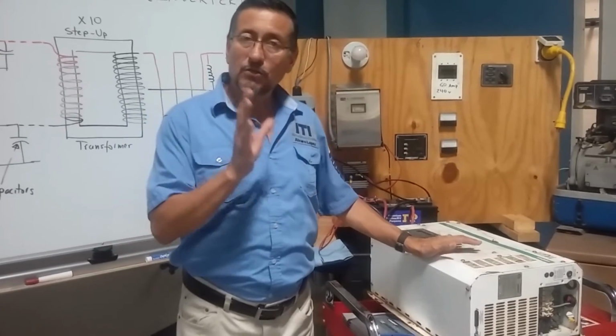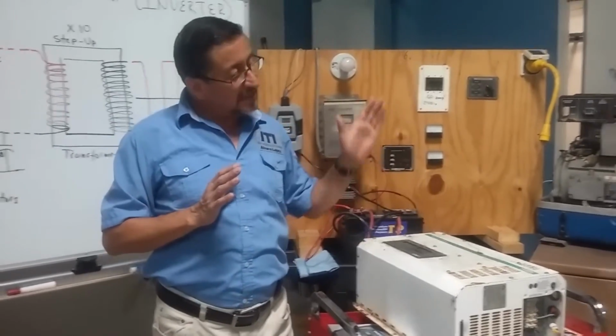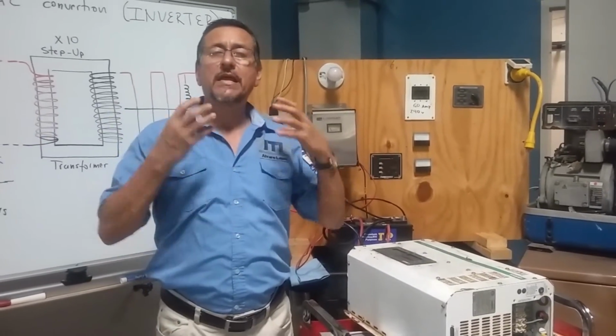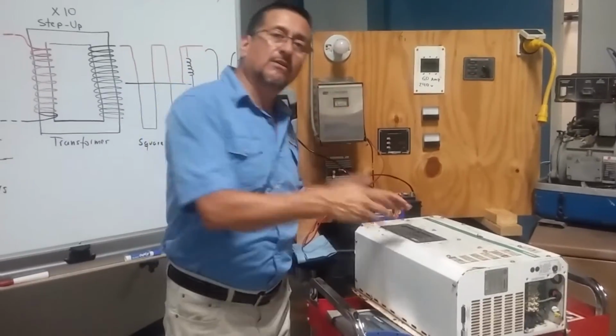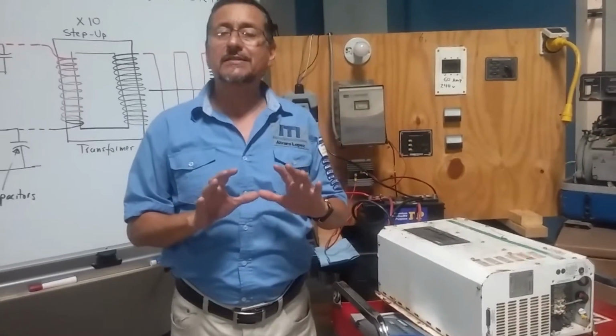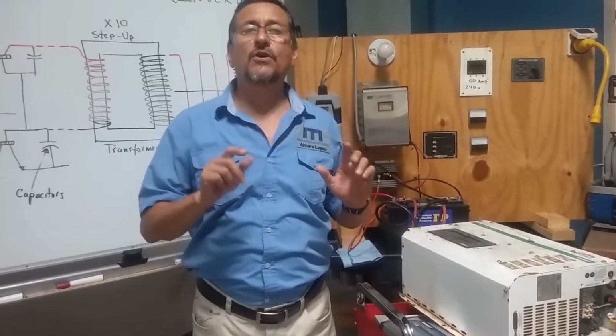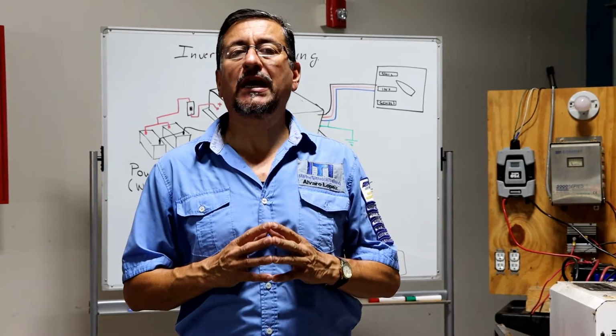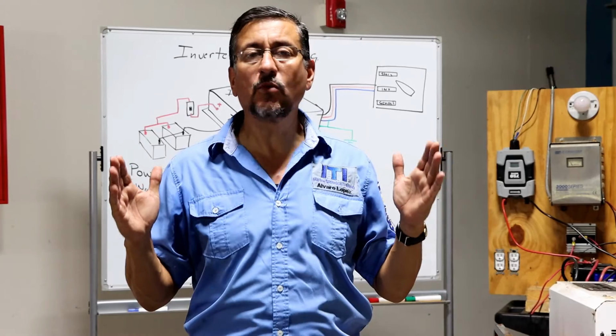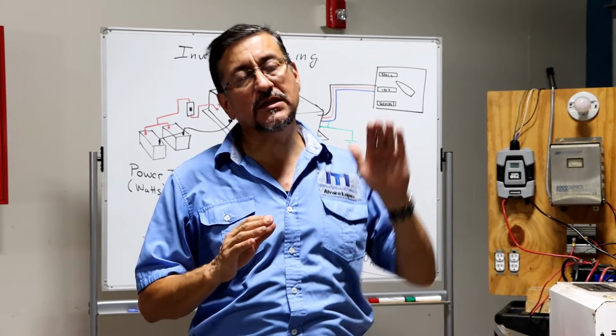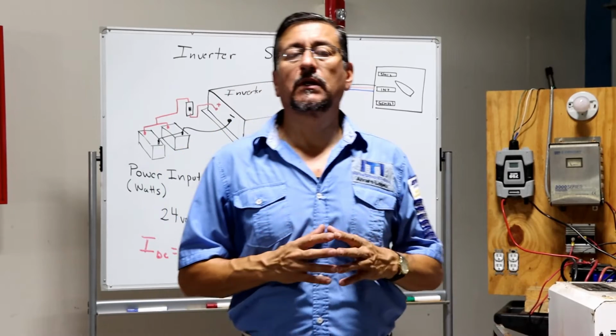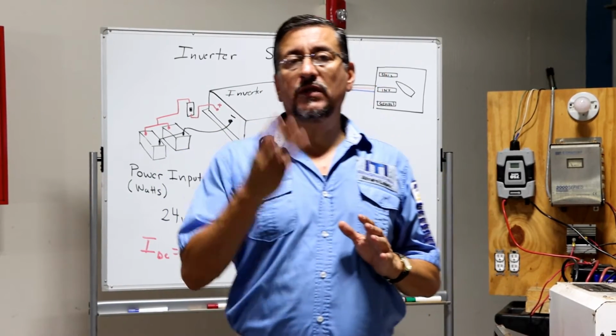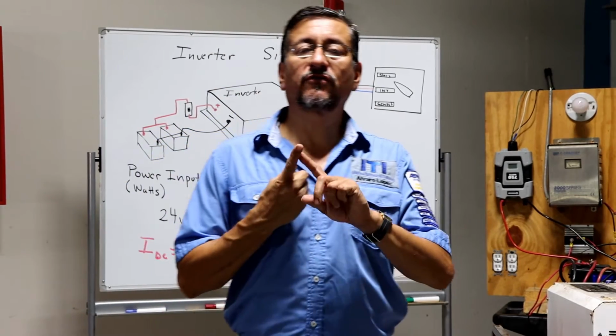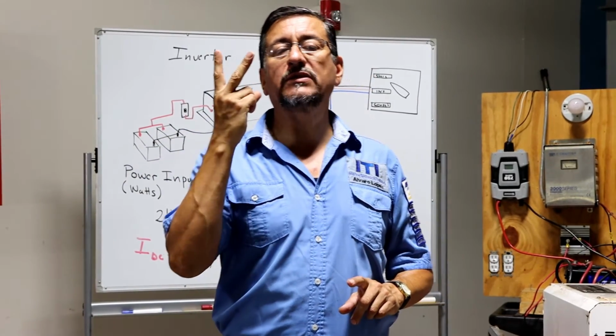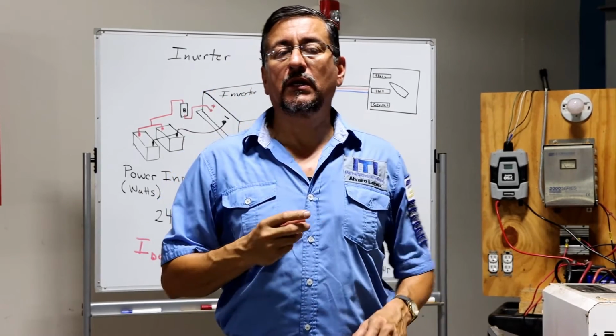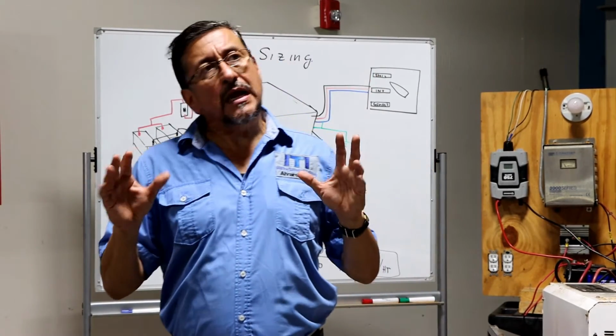For that reason, I am going to explain later the procedure to install the inverter, what type of breakers on the panel should be recommended for the inverter, and what type of breakers are not recommended. I am going to explain the procedures to calculate the capacity of the inverters in kilowatts, and the procedure to install the inverter on the boat. Remember, the inverter is one of the three sources of AC power. One source of AC power is the shore power, the second one is the generator, and the third one is the inverter.